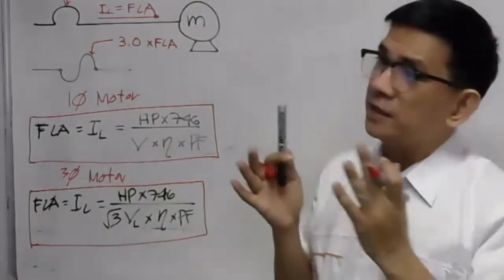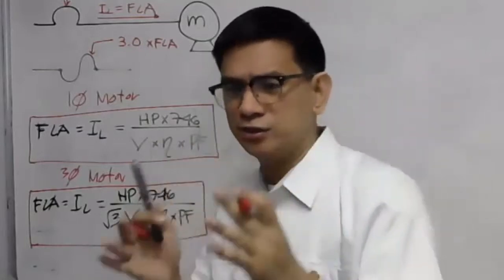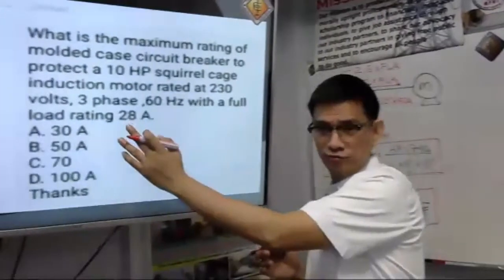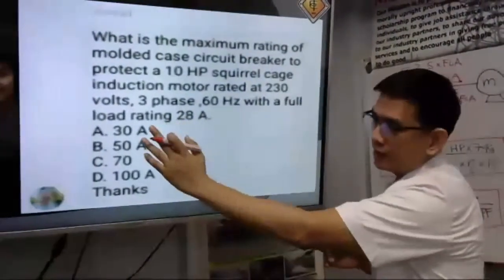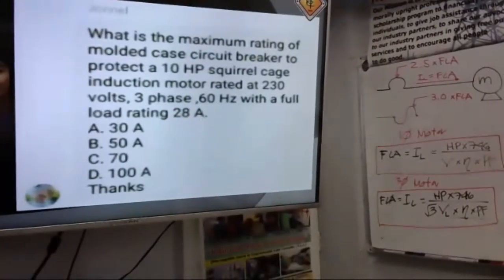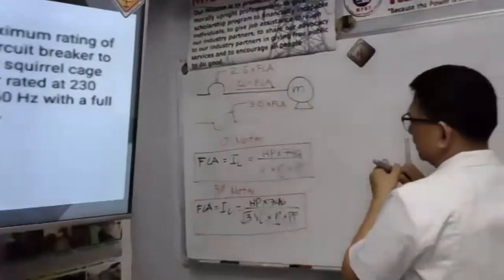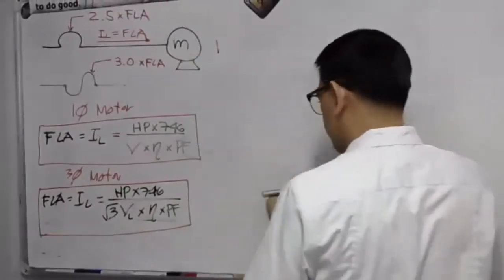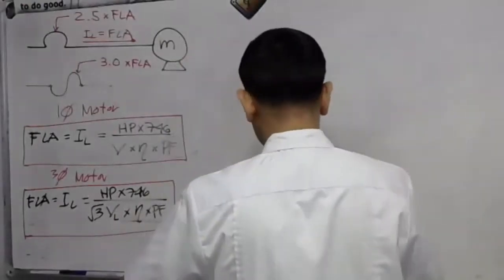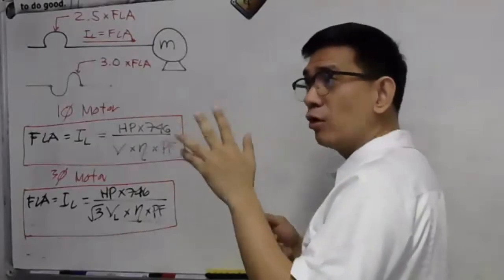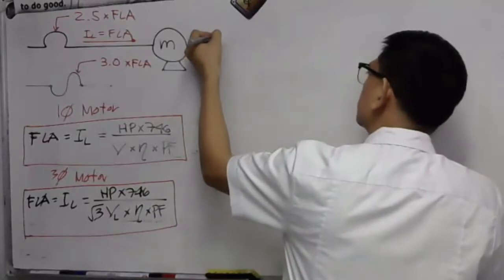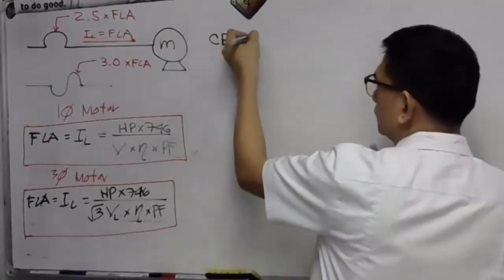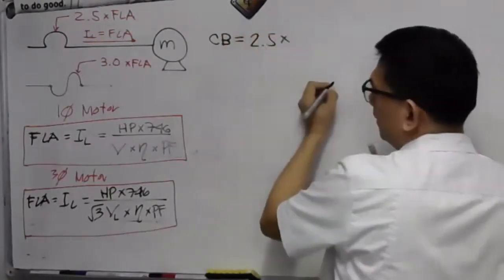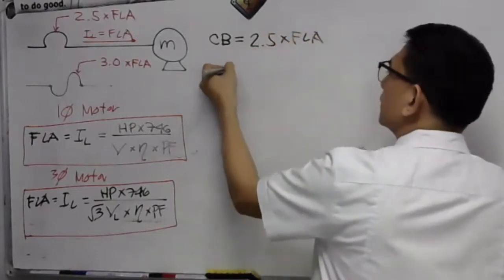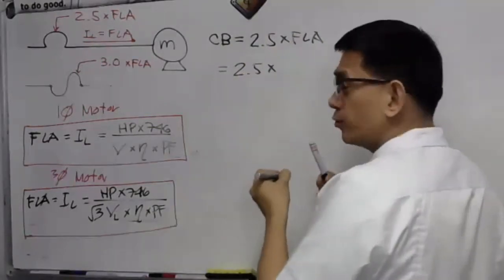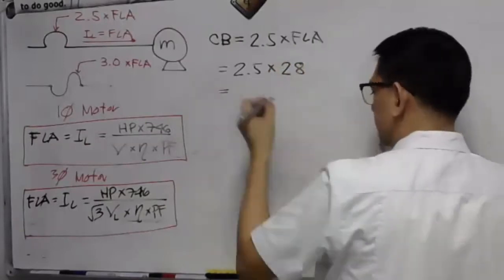So, we are given here a 3-phase motor. But the easier thing in your question is that the full load ampere is already known. Binigay mo na, Junel, 28 ampere. Kaya madali na lang 'yan. Let us have now the size of the circuit breaker, because the question is the maximum rating of the molded case circuit breaker. So our circuit breaker is equal to 2.5 multiplied by the full load amperes. We have here 2.5 multiplied by 28, your given, and I will calculate this.